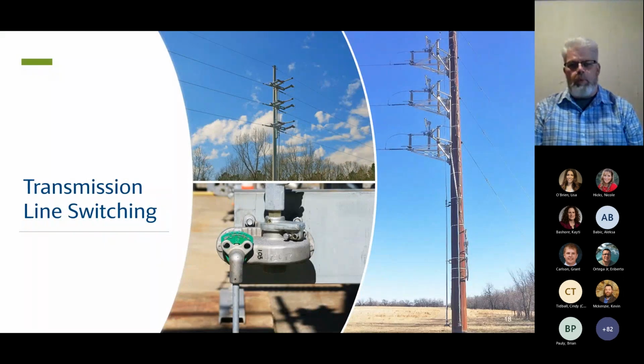Sometimes we have to open pole switches and de-energize sections of line. What you need to think about when operating a pole switch is: what type of switch is it? How long of a line am I going to de-energize when I open the switch? And do I have anything mounted on the switch that will help extinguish the arc?